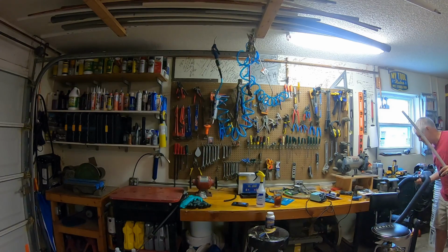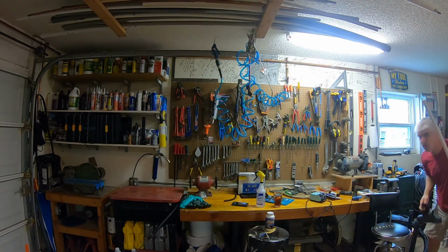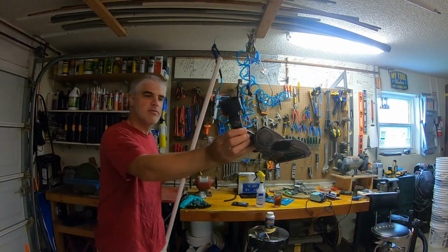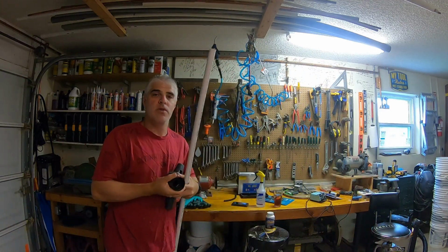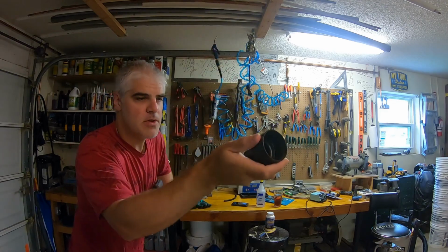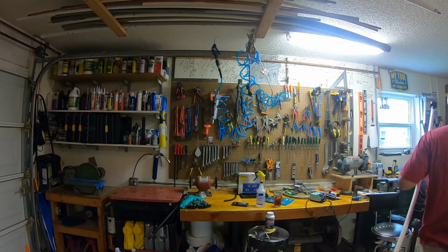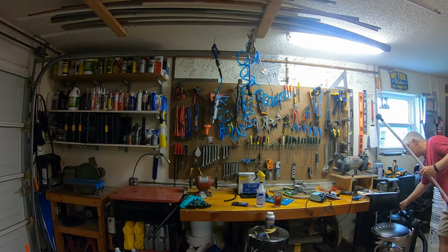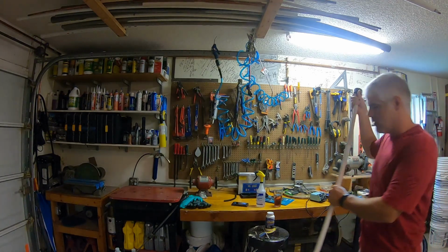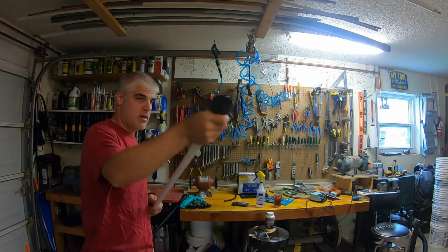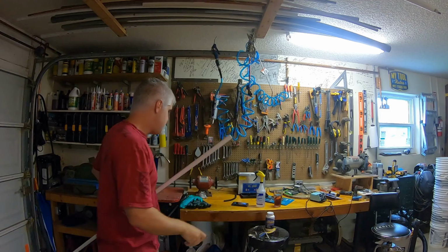It's to adapt a larger hose to go on a smaller tool like this. So that's what it's designed for. But you can also use it to hook your shop vac up to 3/4 inch PVC and suck the drain line out. So that becomes a very inexpensive, cost-effective way to clear the line. Sometimes the clog will come out very easily. Other times you kind of have to pulse it. So that's one way.